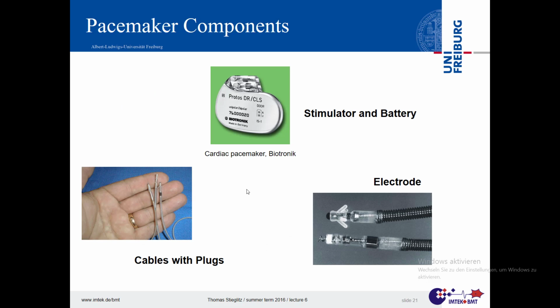We have the stimulator and the battery, and you find that quite often under the abbreviation of IPG, implantable pulse generator. You need some connectors to connect the cables. You have cables with plugs that fit in there, and indeed there's a worldwide standard that you have the same plugs for the cables, so that you can buy the cardiac pacemaker. Not you, but you as a medical doctor could buy the cardiac pacemaker from one company and the lead from another company, for example. And we have those electrode leads that go into the heart, and they have to get fixated.